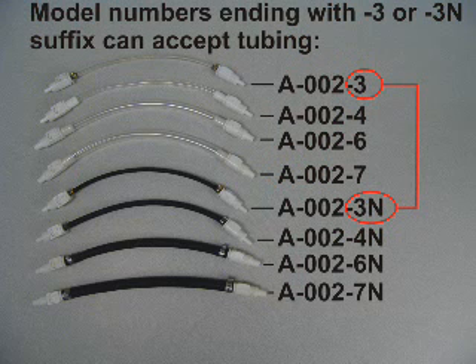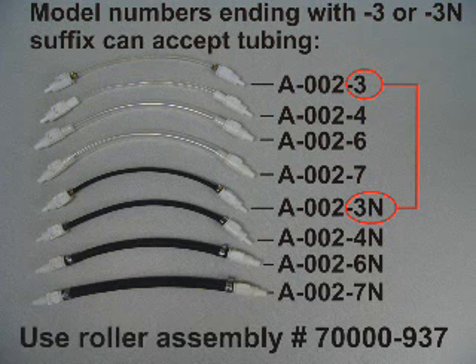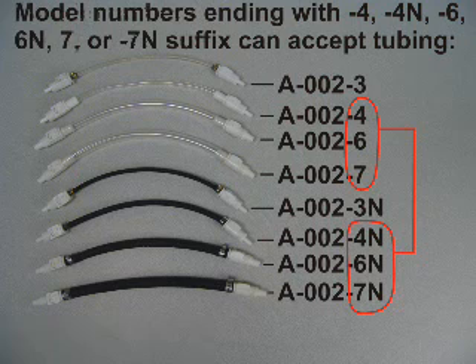Model numbers that end with the suffix dash 3 or dash 3N can accept pump tube part numbers A-002-3 or A-002-3N. The roller assembly that must be used with these tubes is part number 70000-937.